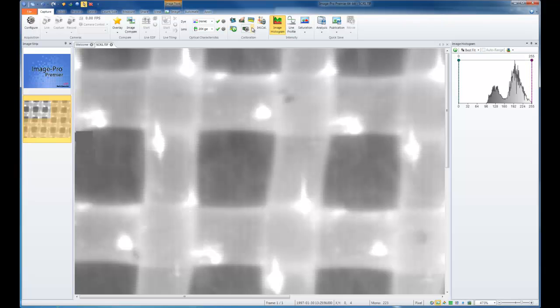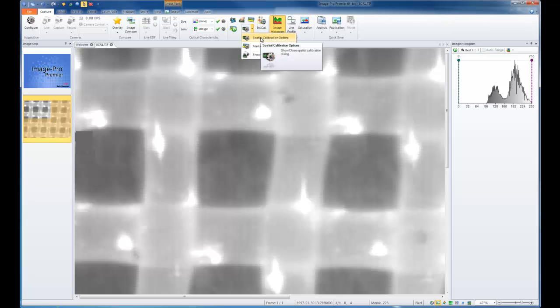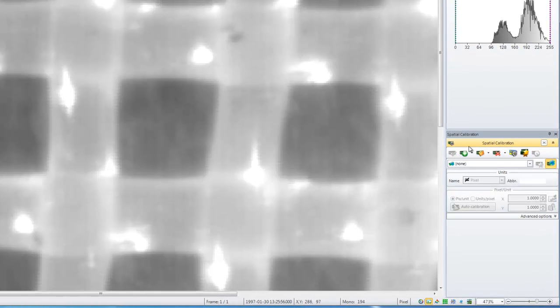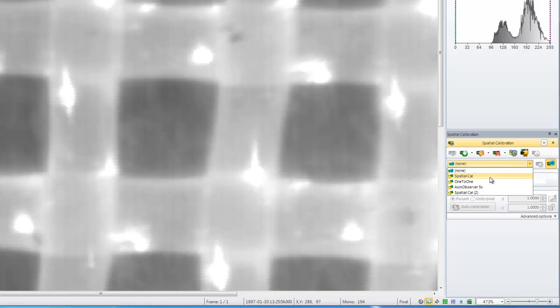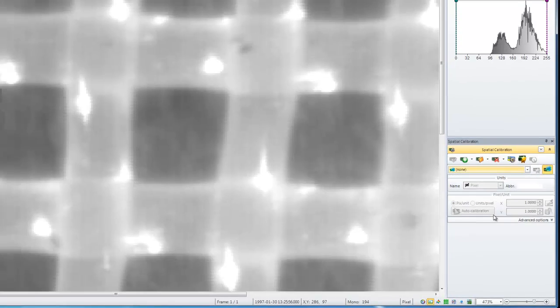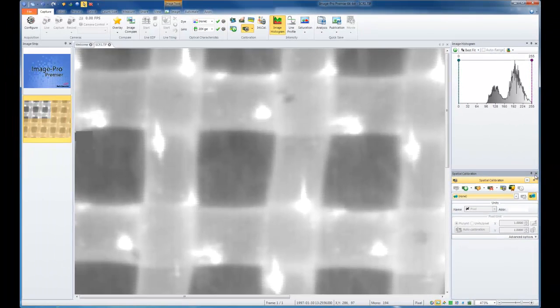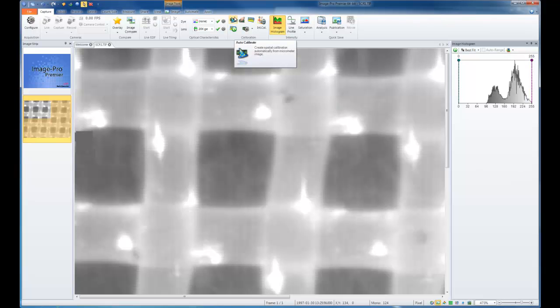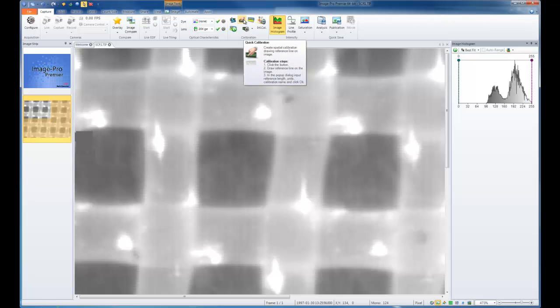To access your calibration information, choose the drop-down and go to Spatial Calibration. This is only going to be used if the image that you're opening does not have calibration data already attached to the image. With this open, I can then select my calibration information from any available calibrations already created. If nothing has been created previously for the system, I can create one by either using the wizard, using our Auto Calibrate function, or I can draw a line as a quick calibration to a reference on the image.